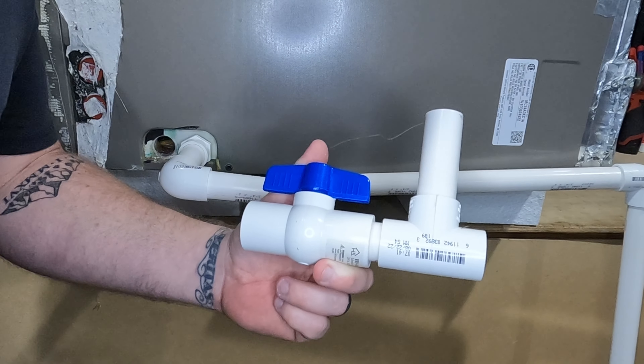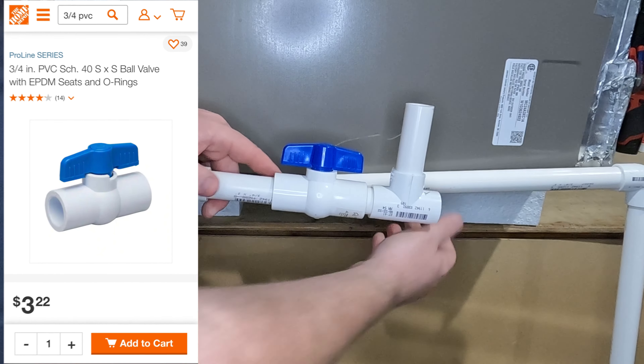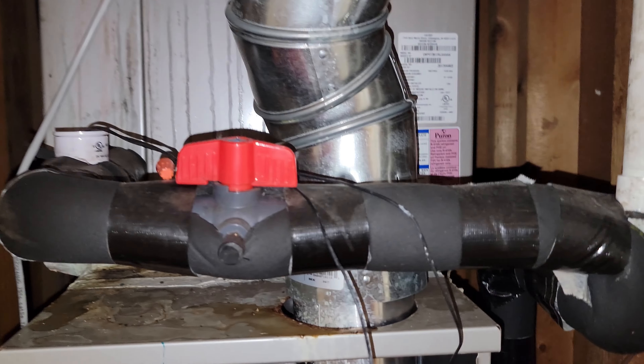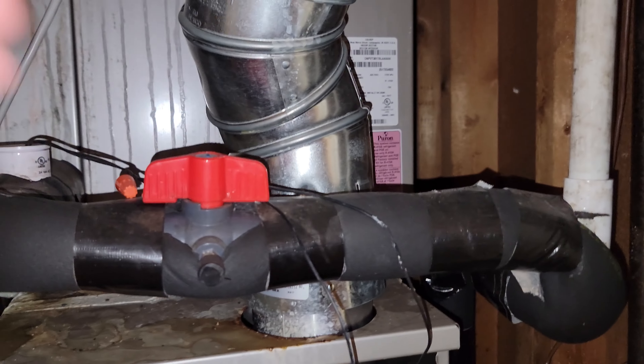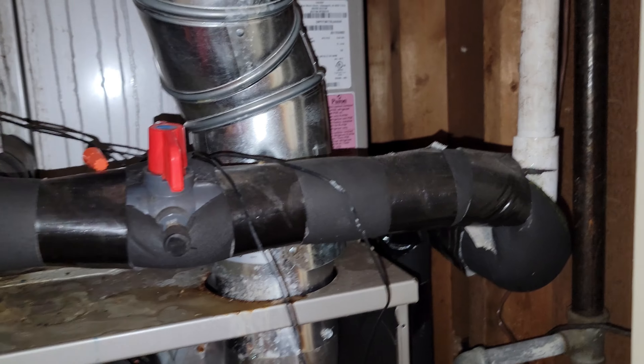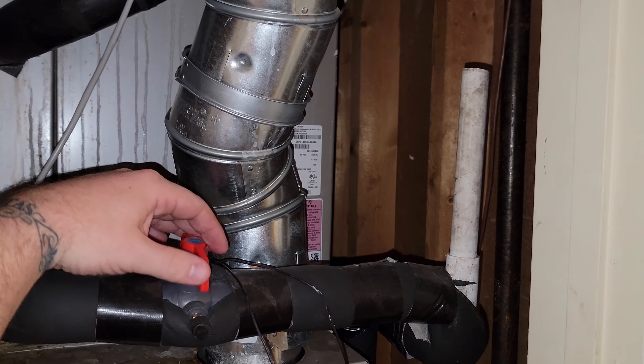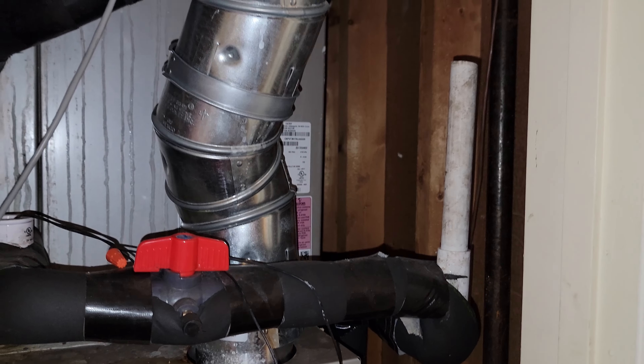Another setup you can put in your drain line is a ball valve and T system. Once you glue this whole thing together onto the drain line, it actually allows you to flush out your drain line in the future without having to take it apart. All you have to do to service it is shut off the ball valve, flush it out through your T, and the ball valve will keep anything from coming towards the coil and always keep any pressure going towards your downside.